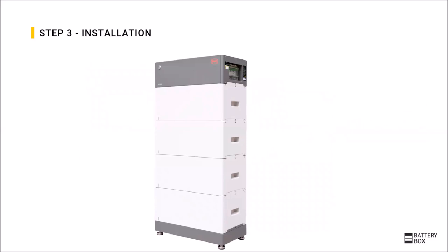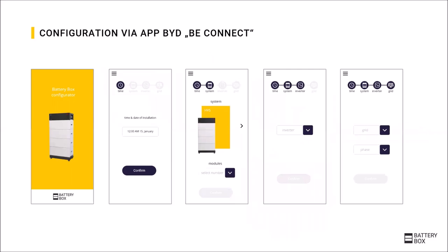For commissioning, you simply switch on the battery using the system switch on the right side of the battery. And then configure the battery using an app that is available via the Android or Apple app store. The app is called beConnect and only a few quick steps are required for commissioning such as the date, the module configuration, and then voilà. This is about all for the Premium HV.